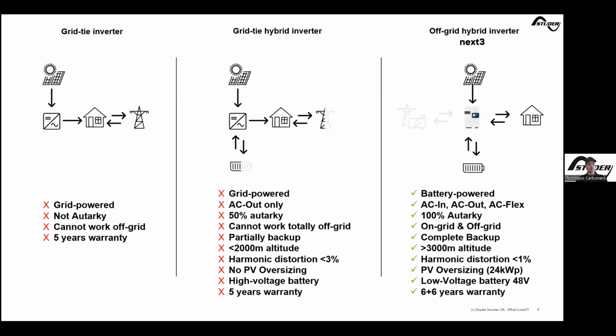So what is the advantage, the pros of the Next 3? What does it do differently compared to hybrid inverters? As I mentioned, grid-tied hybrid inverters, in most cases since there are different manufacturers, are always connected to the grid. In some cases, there are inverters that cannot work totally off-grid because they need the grid to start producing from the solar. In some other inverters, if you always work off-grid, they can void your warranty. So be aware of that too.